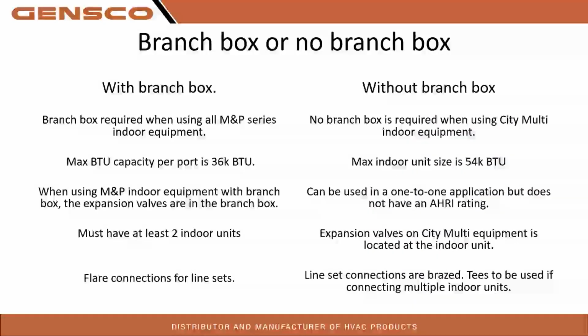So, branch box or no branch box. You will need to use a branch box if you're using any M&P series equipment. This is your MSZs, your SVZs, your PEADs, PLAs, all that kind of stuff. With those indoor heads, you do not have expansion valves in the indoor head, and the Smart Multi heat pump does not have individual expansion valves for all of the indoor equipment either. So your indoor expansion valves, or metering device, are actually located in your branch box. That is required anytime you're using the M&P series product. If you are using a branch box, be aware that you can only go up to 36,000 BTUs per port on that branch box. You're not able to twin two ports together to get more than that. 36,000 is the max. So if you're trying to do something like a PEAD 42, it's not going to work. Can't do it.